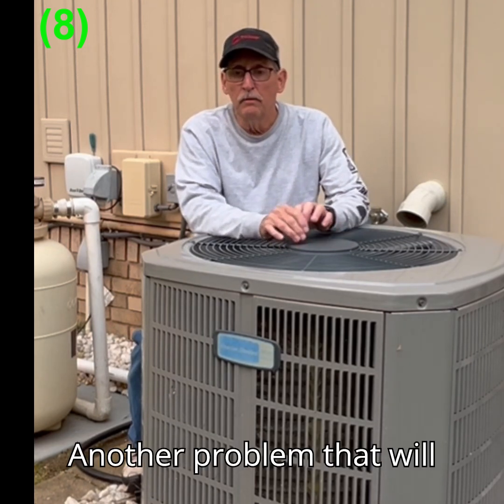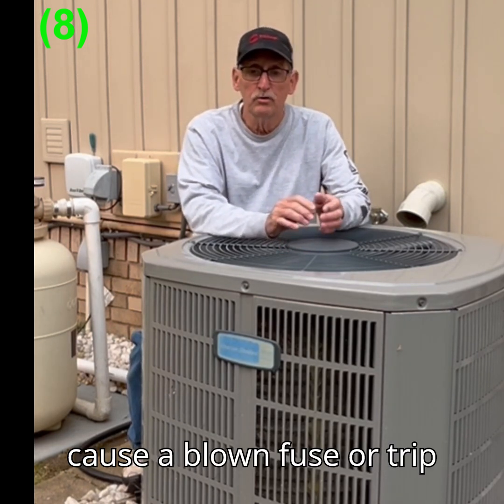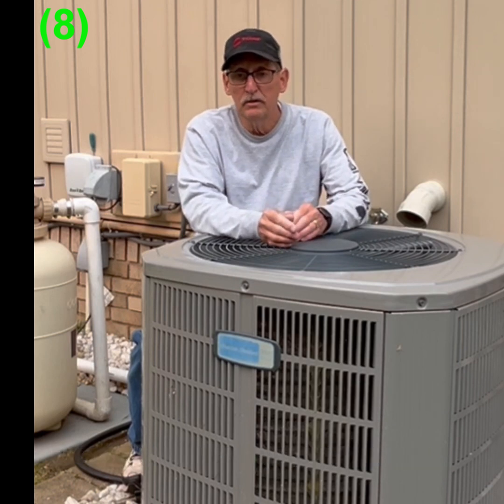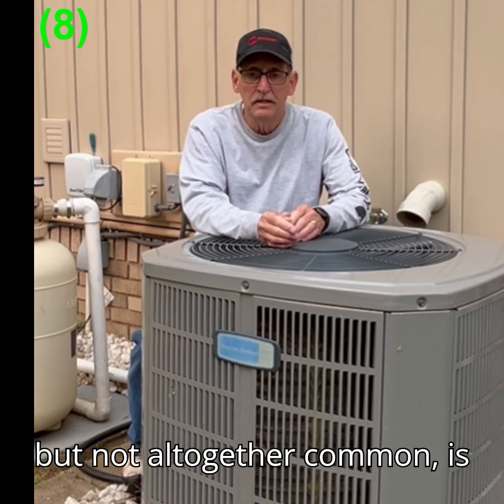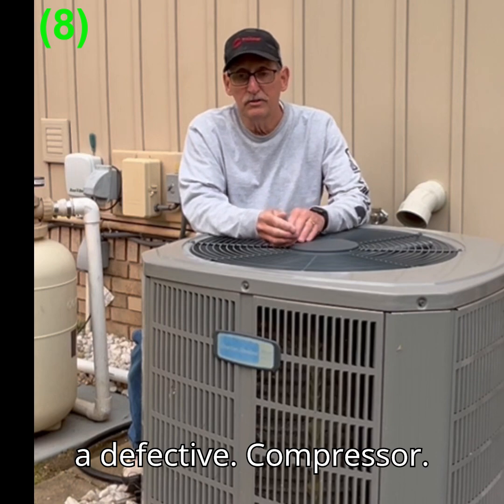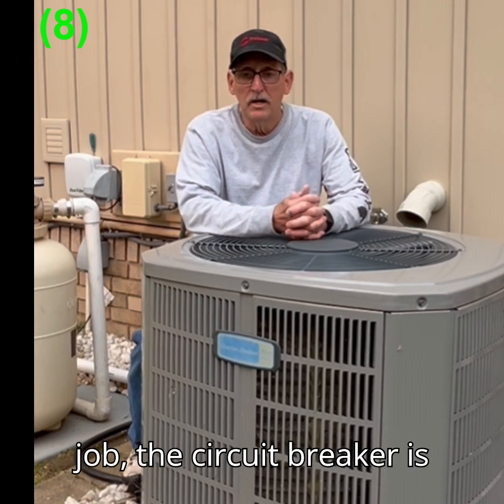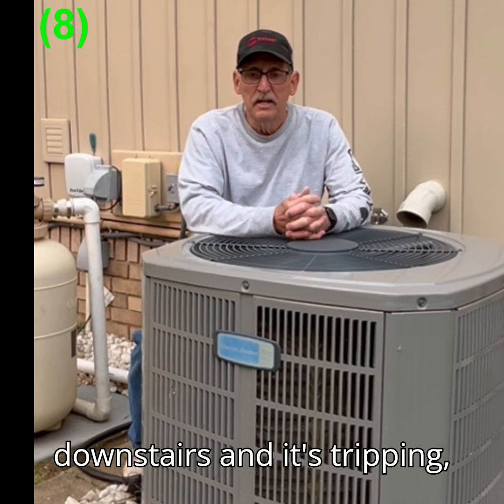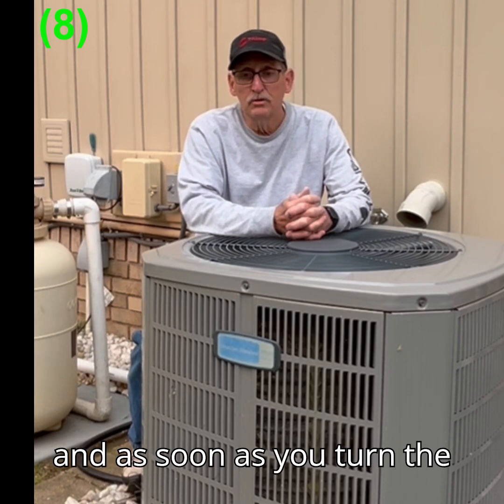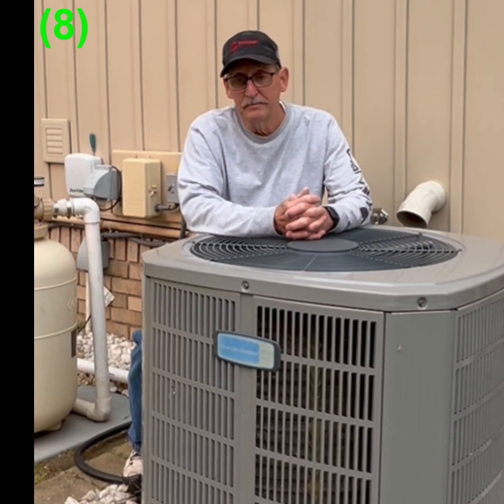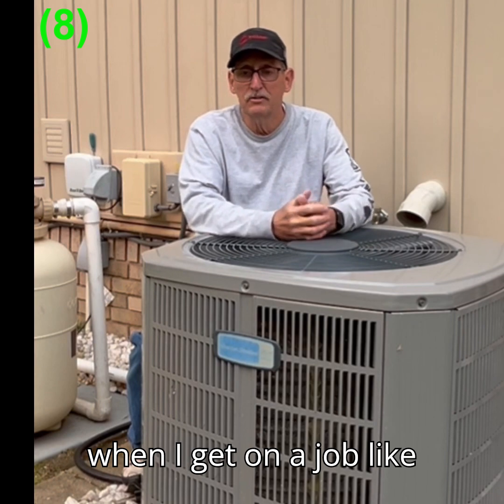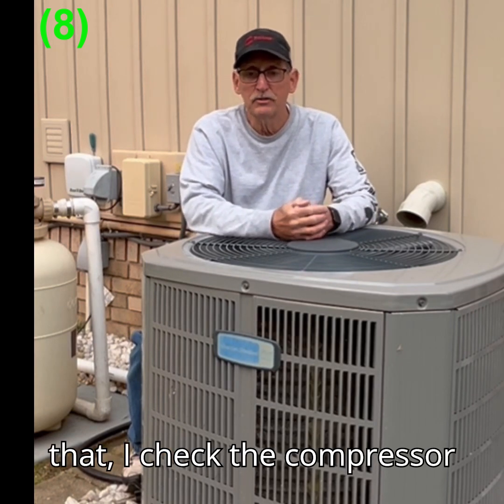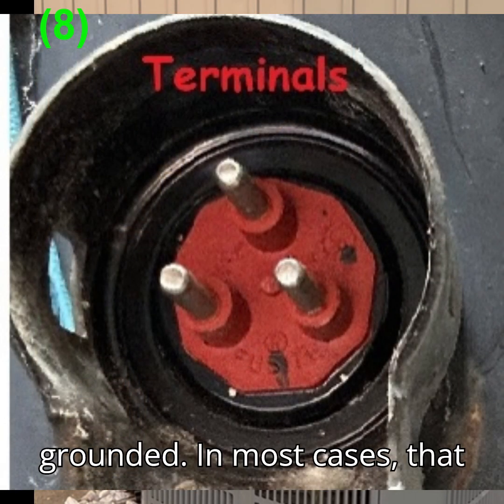Another problem that will cause a blown fuse or tripped breaker on the outside unit, but is not altogether common, is a defective compressor. Usually, when you get on a job, the circuit breaker is downstairs and is tripping, and as soon as you turn the system on, it trips again. First thing that I usually do when I get on a job like that, I check the compressor terminals to see if they're grounded. In most cases, that is a strong possibility.